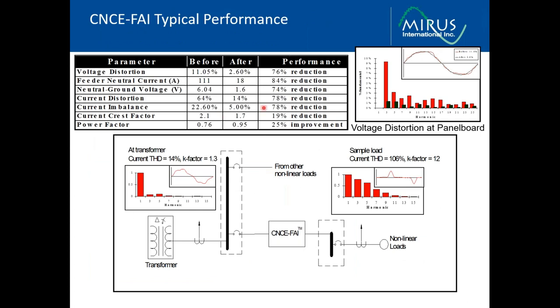Here's an example of an installation where we also did the phase shifting to treat fifth and seventh harmonics as well. The load current was, in this case, 106%, with very high third, fifth, seventh, and ninth harmonics. Upstream of the passive filter application, we were getting near-linear current, much lower current THD and K factor. The neutral current dropped from 111 amps to 18, which lowered the neutral-to-ground voltage, which is the result of current on the neutral creating voltage drops on the neutral. It went from 6 to 1.6.